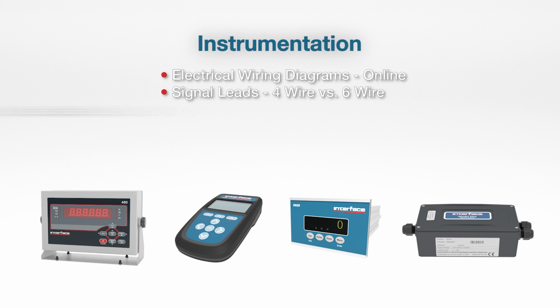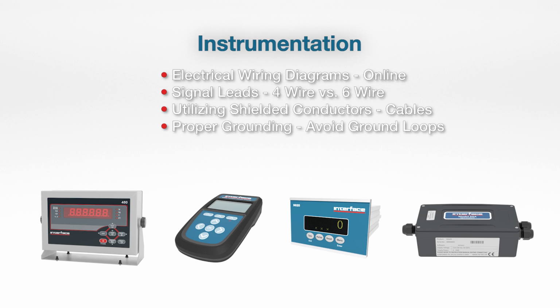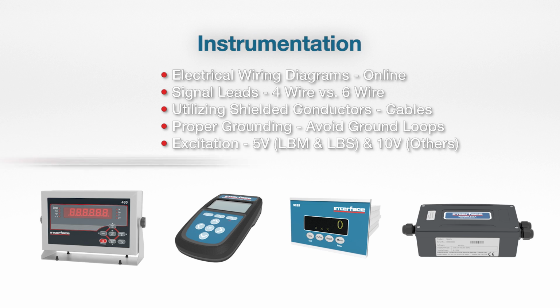Naturally, you're going to want to have some way of interpreting the output, or the voltage, from the load cell. So you're going to be connecting it to instrumentation of some kind in the application. As far as connectivity goes, if you're looking to hook up the load cell and need information on that, the majority of our wiring diagrams are available online. If you're not sure what wiring configuration you have, please do give us a call. We don't mind. We would have that information available for you for any unique option codes you may have.